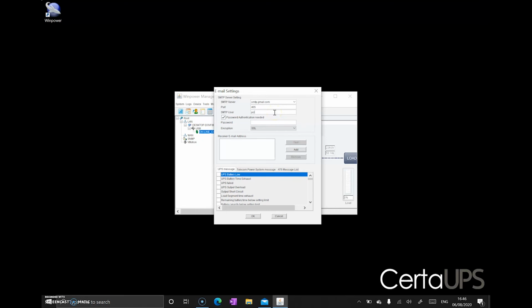Enter your username and password, then add a receiver's email address. I'll use the same email address for this demonstration that we've used to actually send the emails. Tick that, and underneath you can see a list of UPS messages you're interested in. For us, we'll set UPS battery low, UPS output overload, AC fail on bypass, and press OK.